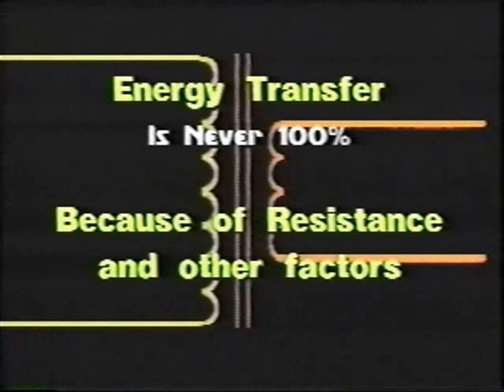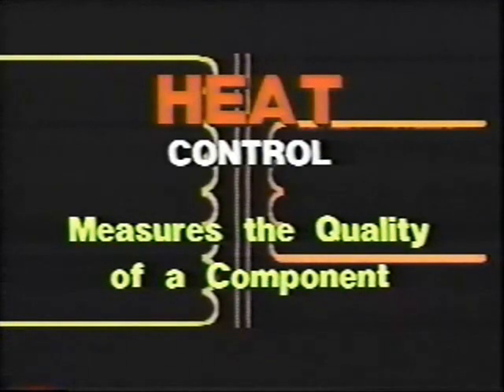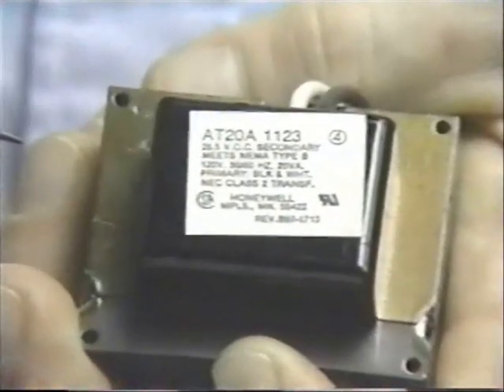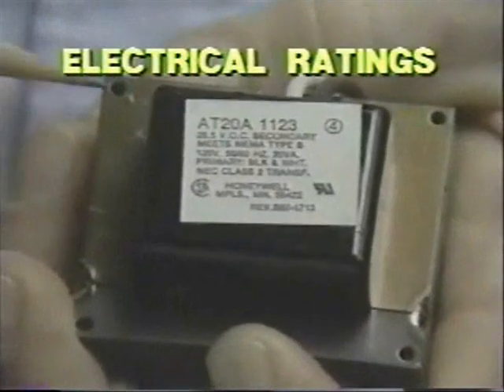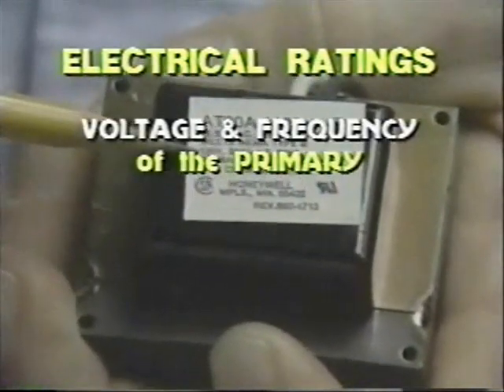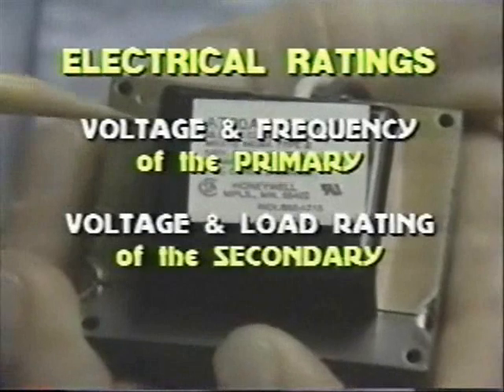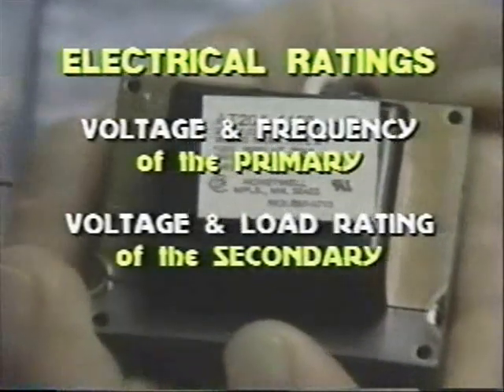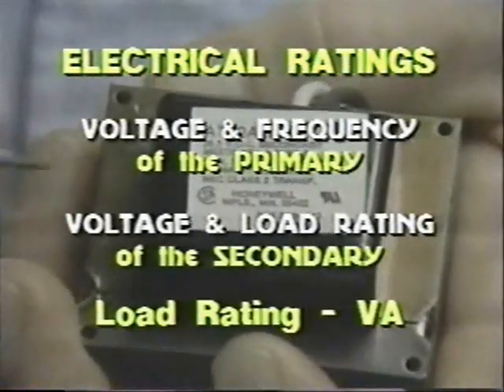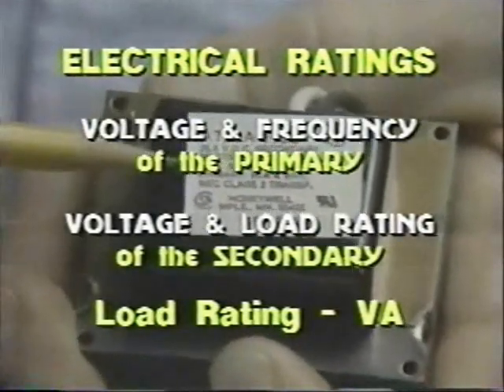In either case, energy transfer between the two coils is never 100% efficient because resistance and other factors cause heat buildup. Heat, of course, is the enemy of electrical equipment, and one important measure of a component's quality is how well it controls heat buildup. A transformer's capabilities are indicated by its electrical ratings. These include the voltage and frequency of the primary and the voltage and load rating of the secondary. The load rating is expressed in VA, which is volts multiplied by amperes.